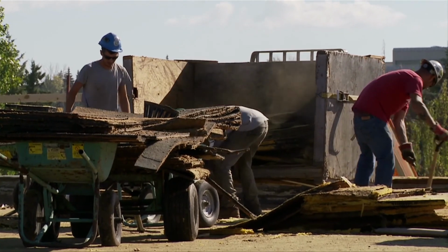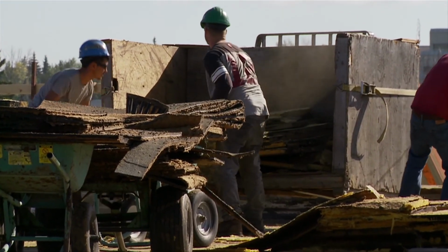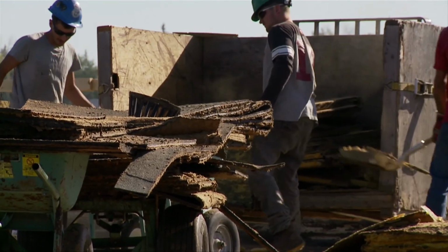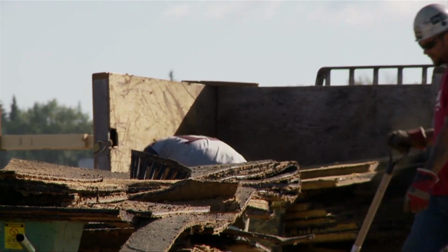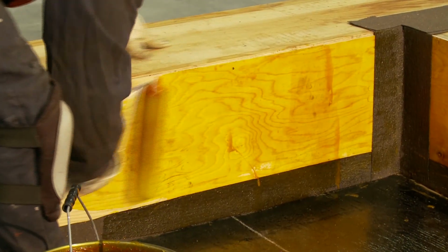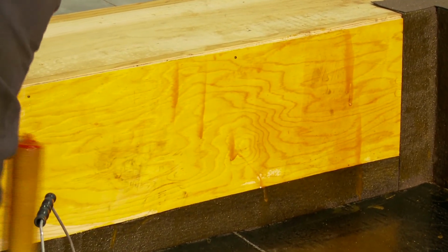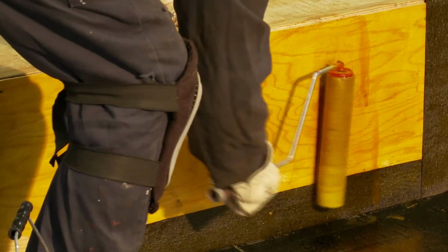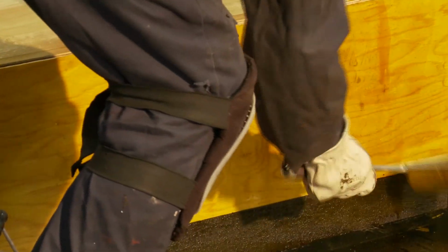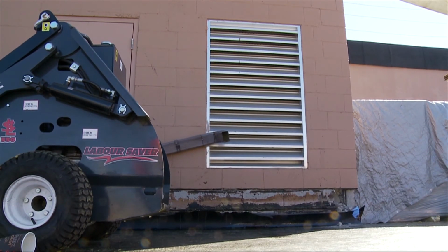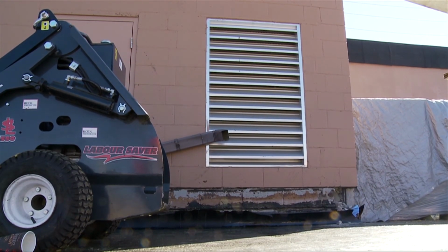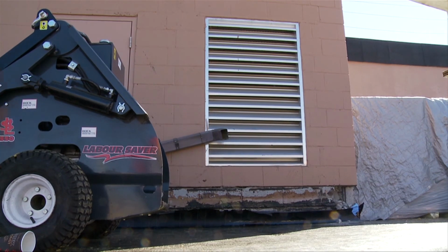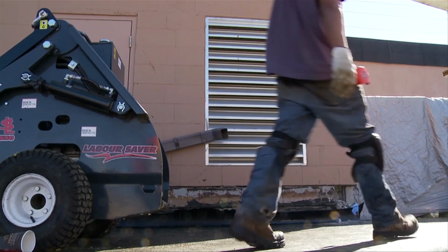Environmental conditions or weather effects. Temperature. The air temperature may increase flammability or combustibility of substrates and roofing materials. As the temperature decreases, primer flash-off times increase. High wind speeds reduce flame intensity and may deflect intended flame direction. In unsheltered locations, the flame may be pushed into unprotected building openings and substrate voids and may be the cause of a fire.